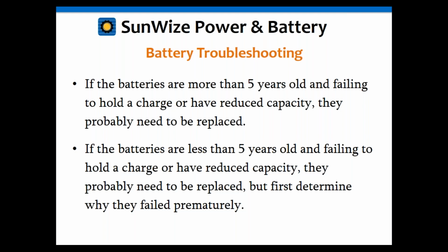But again, before you put in a brand new set of batteries, you may want to just double check, make certain your system is functioning correctly before you damage a new set and find yourself replacing brand new batteries every few years. Batteries are very expensive. They're about 40% of the cost of the system nowadays, so they're probably one of the single most expensive components. You want to try to get as long a life out of them as possible. And again, we'll go into that more in our next webinar on battery basics.